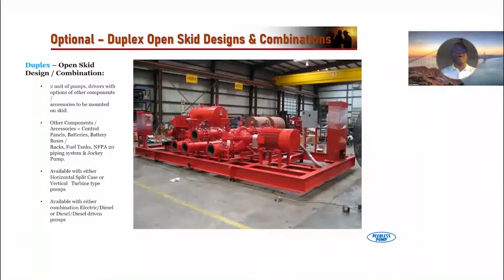The skid just gets a little bit larger. Here's a picture I'm showing. On the right-hand side, that's the electric driven pump, and this is the electric controller. On the left side, you can see the diesel engine, the diesel tank, and here's the diesel controller. You can see a common suction piping for the electric, which will run clockwise because diesel only goes one way, and all the discharge will be on the other side. So the customer basically has to bring in the common suction header onto this when you get to the job site, bring the power in, and then you're good to go.